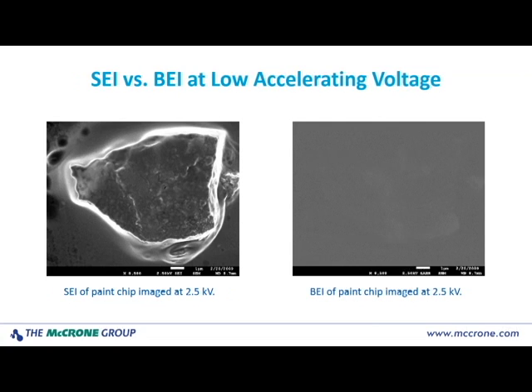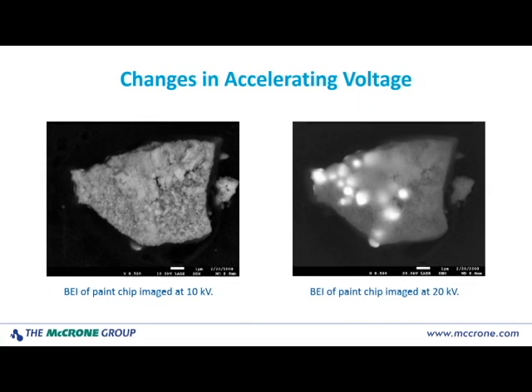Let's take a look at the same secondary image on the left at 2.5 kV, and we switch from the secondary detector to the backscatter detector. We don't hardly see a particle — you can barely make out there's something there. There's just not enough signal under those conditions. We could change something to improve on that — change maybe the brightness and contrast, or change the number of electrons going into the sample without changing the kV — just to create more signal and start to bring this particle out. But another way to do it is just change our accelerating voltage. We've gone from 2.5 up to 10 kV, and we can see some very nice structure in the backscattered image in compositional mode, with different brightness contrast levels showing up.